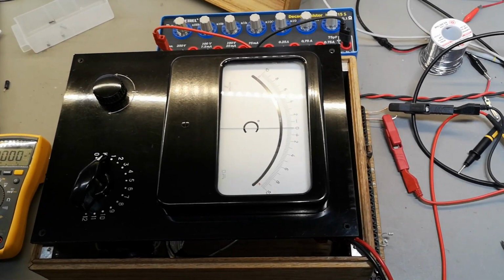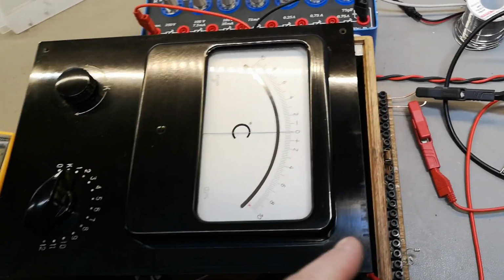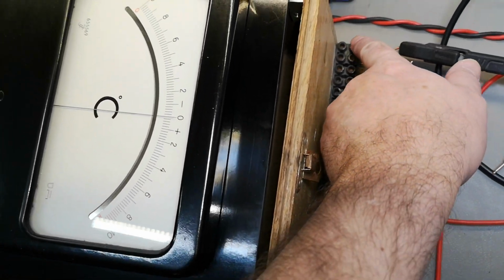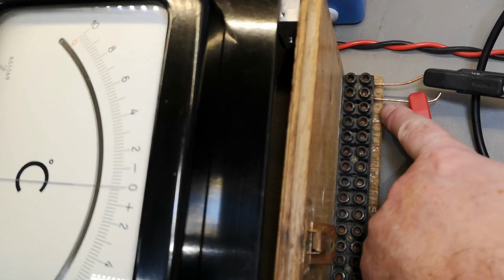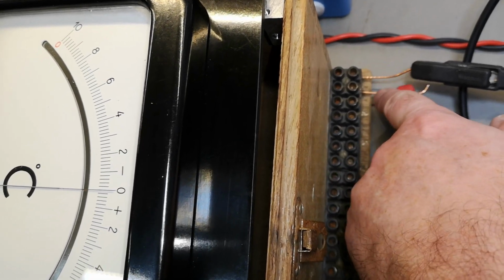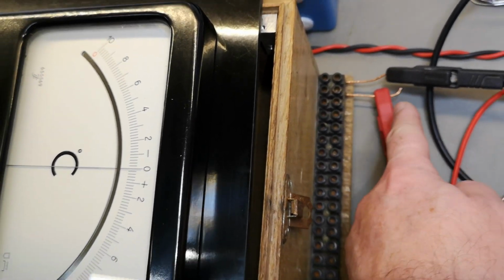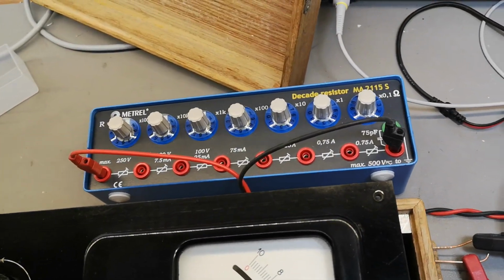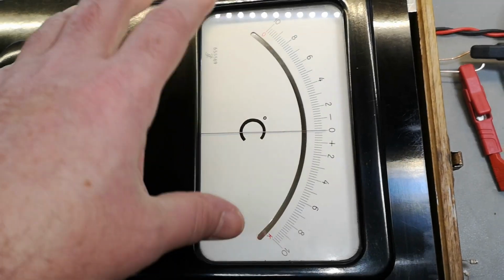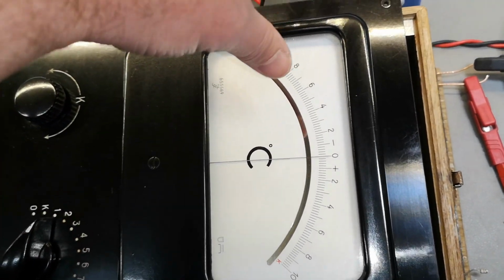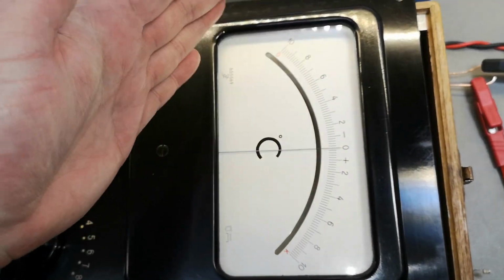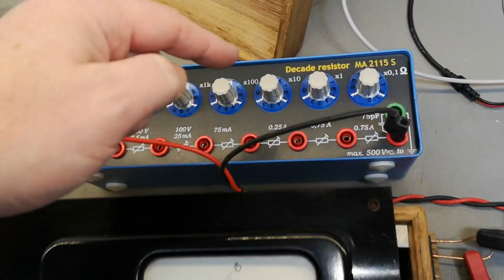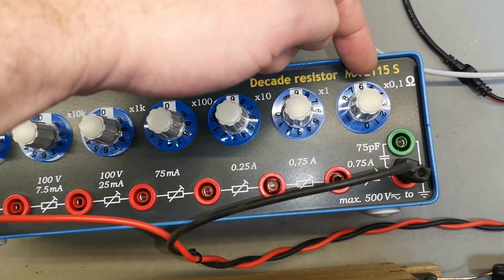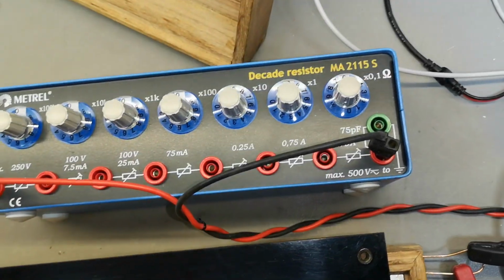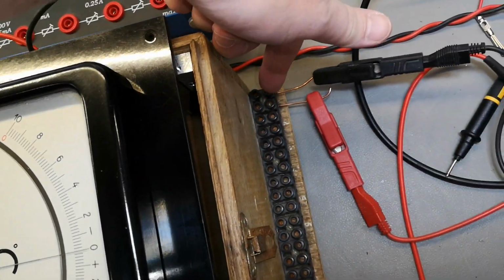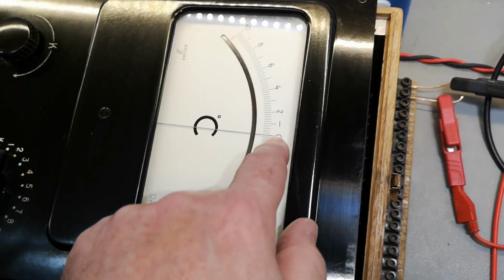This is really funny, I've actually figured this out now. So every sensor, you need 2 wires for each sensor. It says like here 1, 2, 3, and so on, right? So I screwed in these wires here, so this cable goes to this resistor box. So to get this in 0, there's actually a bridge in here, so that means if it's open or if it's shorted, it hammers to both sides. So to have this in 0, we need 99.6 ohms in here plus this cable, so that's probably 100 exactly on the terminals here. It's that accurate to give it a 0 here.